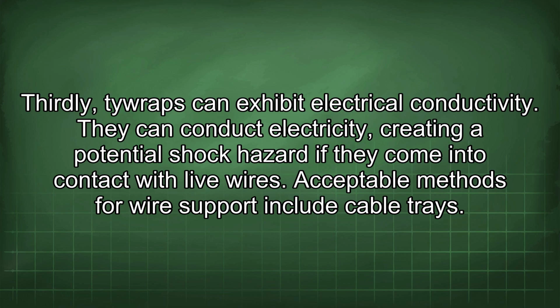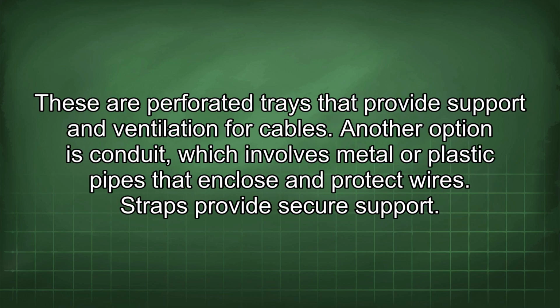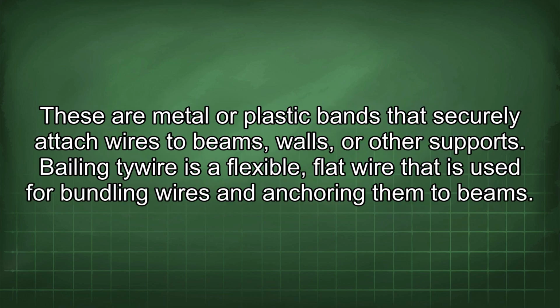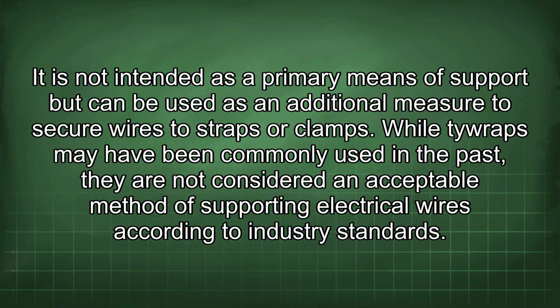Acceptable methods for wire support include cable trays. These are perforated trays that provide support and ventilation for cables. Another option is conduit, which involves metal or plastic pipes that enclose and protect wires. Straps provide secure support. These are metal or plastic bands that securely attach wires to beams, walls, or other supports. Baling tie wire is a flexible, flat wire that is used for bundling wires and anchoring them to beams. It is not intended as a primary means of support, but can be used as an additional measure to secure wires to straps or clamps.